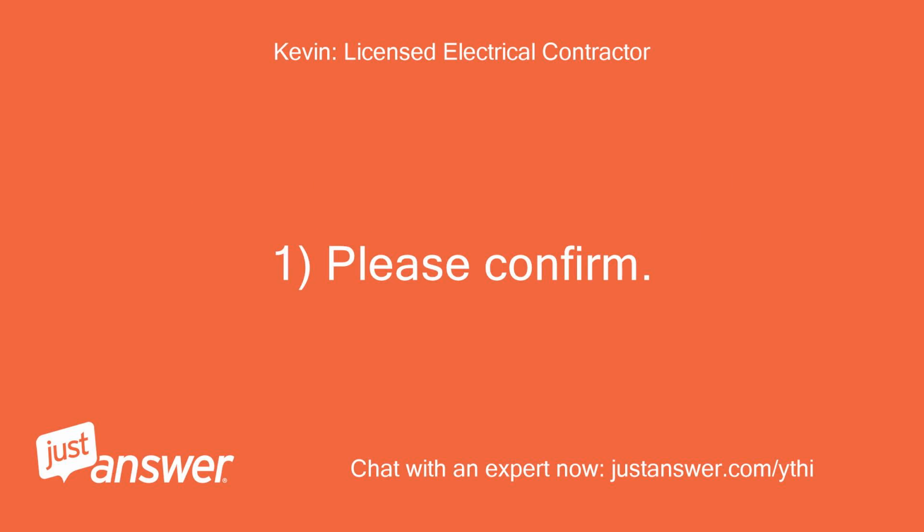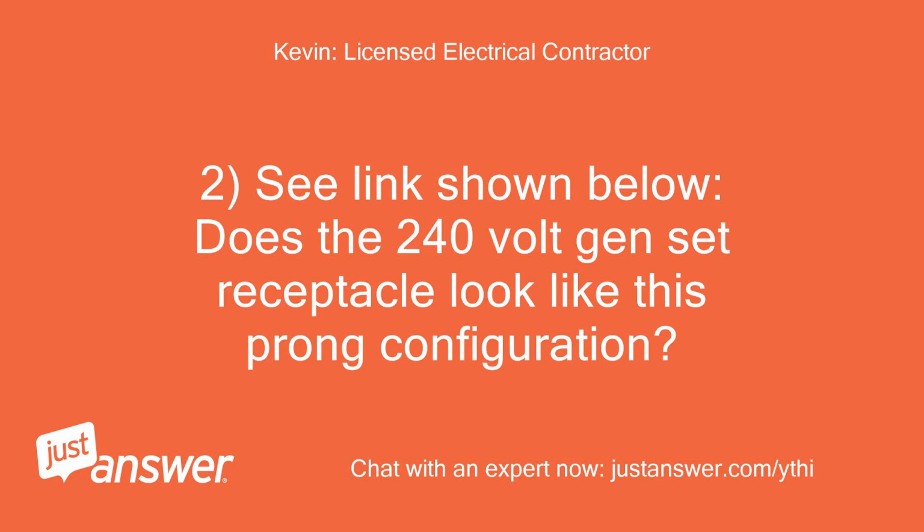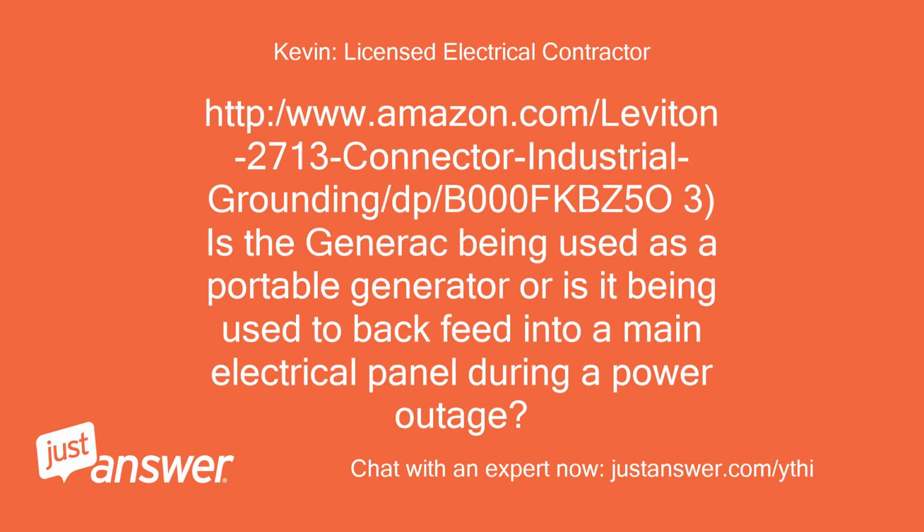1. Please confirm. Is the 240-volt generator receptacle a NEMA rated L14-30R, a 4-prong/twist lock type? 2. See link shown below. Does the 240-volt gen set receptacle look like this prong configuration? Is the Generac being used as a portable generator or is it being used to backfeed into a main electrical panel during a power outage?